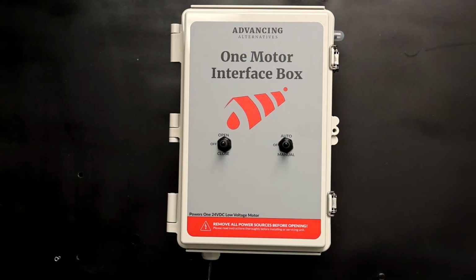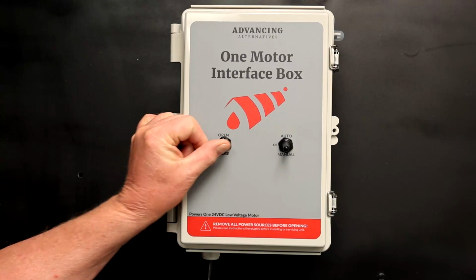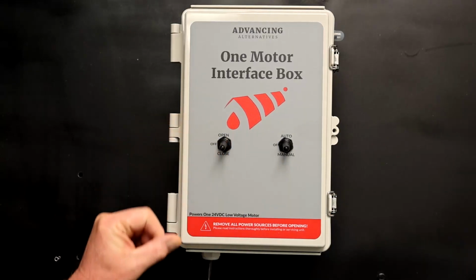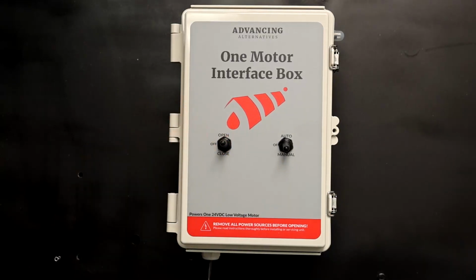If you want manual control of a motor, the switch can be set to manual, and then the open and close will open and close your vents, off in the center position. If you have a remote control capability from a controller or some other relay, you can set the switch to auto and it will be controlled remotely.